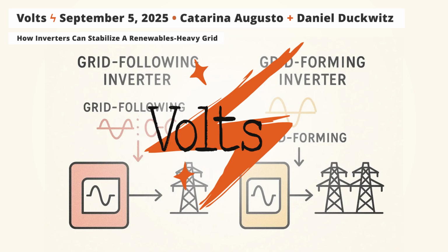Are there things that grid forming inverters can do for the grid that spinning masses cannot do? Are we getting anything extra with this substitution? There are some advantages, because you can program the behavior. For synchronous machines with their turbines, there's a tendency for oscillations between the turbines, the generator, and the grid. These oscillations require additional damping controllers in the power plants, and these can only be tuned so well.